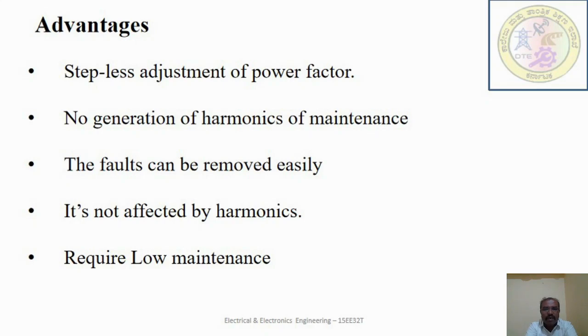Step-less adjustment of power factor. It's not affected by harmonics. It requires low maintenance. That means only periodic bearing greasing if it is necessary. If you see the disadvantage of the synchronous condenser, there are considerable losses in the motor. The maintenance cost is high and it produces noise because of the rotating part. Except in sizes above 500 kVA, the cost is greater than the static capacitor of the same rating.